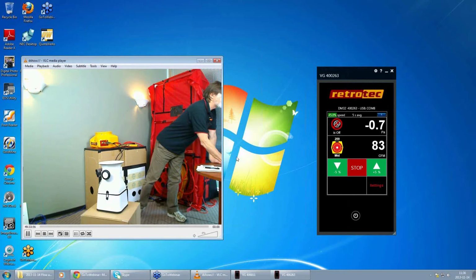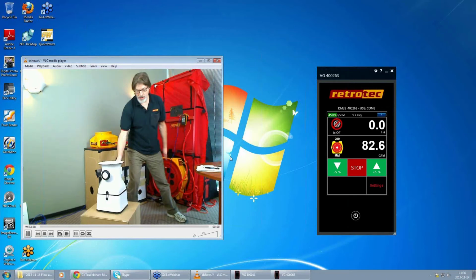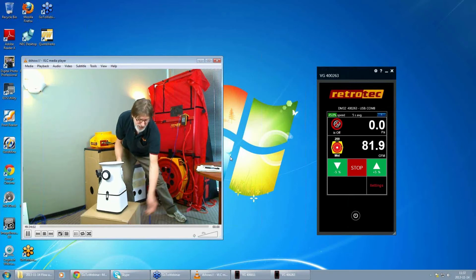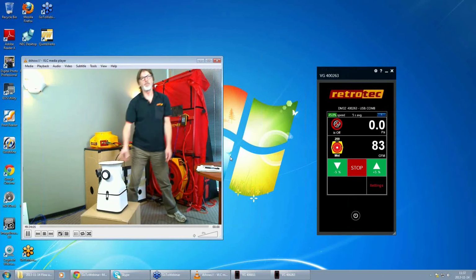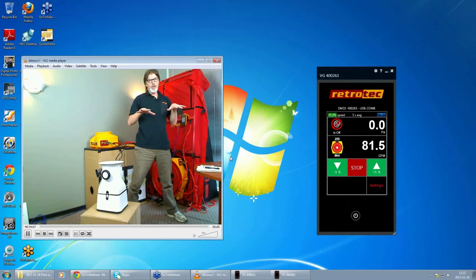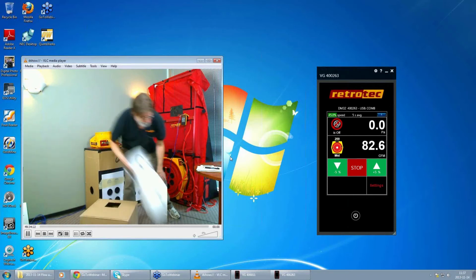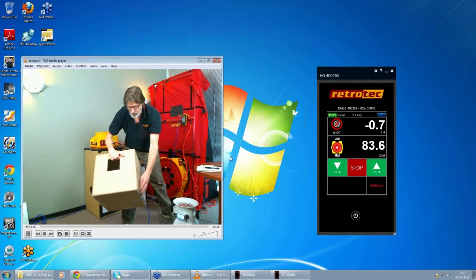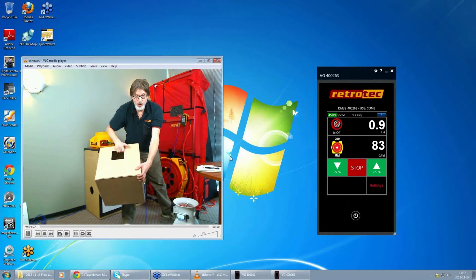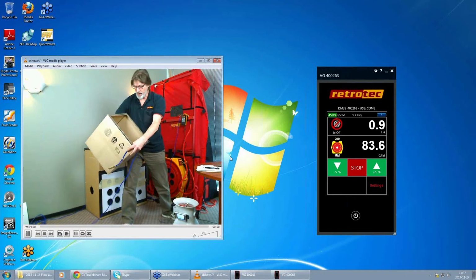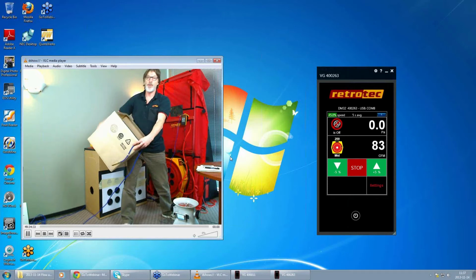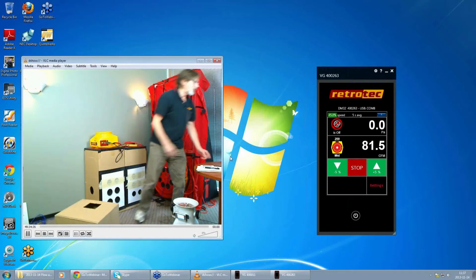Somebody said, what happens if you don't use the probe? I'm assuming that's what he said. You can just take a tube and shove it in here. What's nice about the probe is that it's not affected by velocity as much. It will be more stable, and it allows you to punch it through the box, which is kind of nice. But you could just put a tube through there. Sometimes if you use tubes, you might want to put it at a couple locations, but normally a tube through the box in this area, which is very stable from airflow, the tube goes through the box in this corner here, it usually will be fine. However, if we have supply flow and air is blowing at it like this, it'll go even crazier than this one did. Those probes are not expensive.